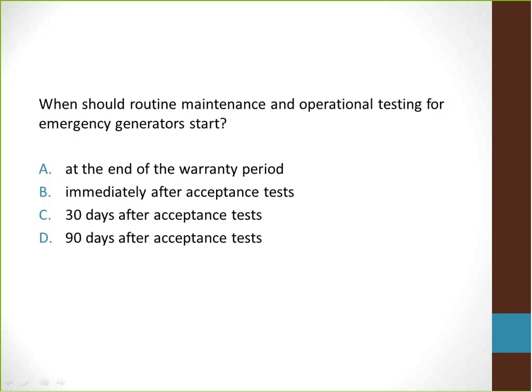When should routine maintenance and operational testing for emergency generators start? A, at the end of the warranty period; B, immediately after acceptance tests; C, 30 days after acceptance tests; D, 90 days after acceptance tests. Answer B is the correct answer here because according to NFPA 110, operational testing shall start immediately after acceptance tests are complete.